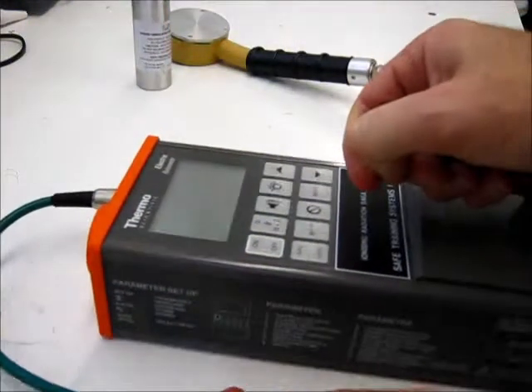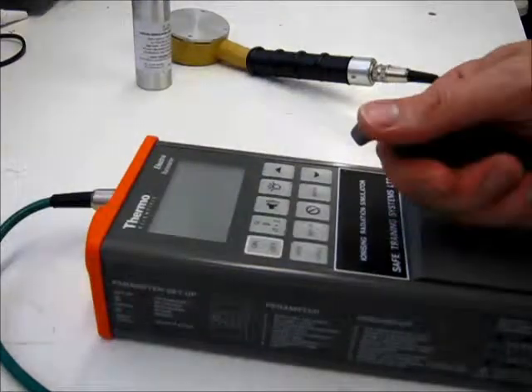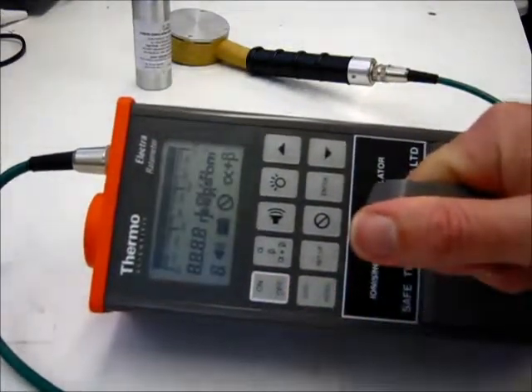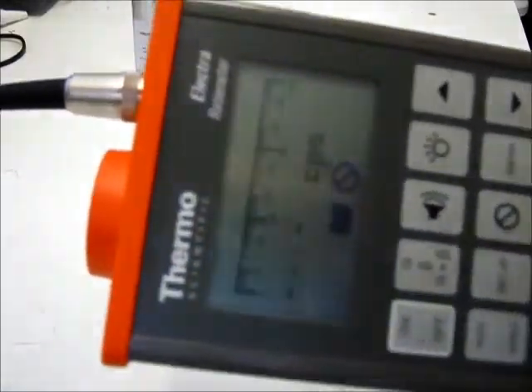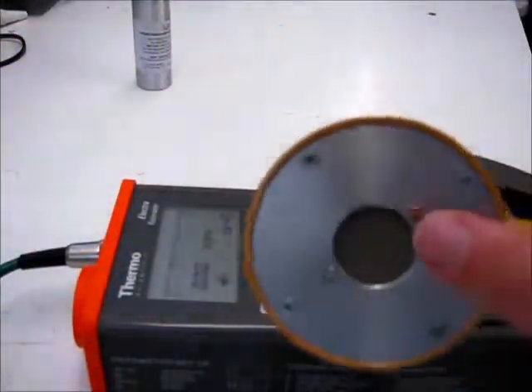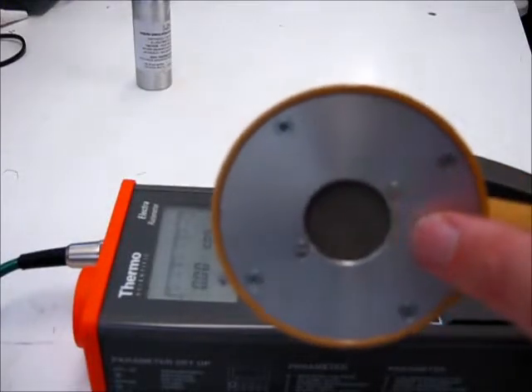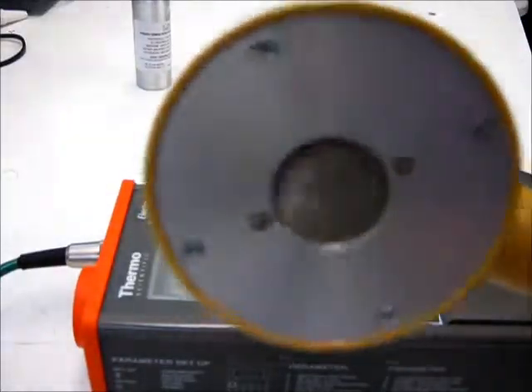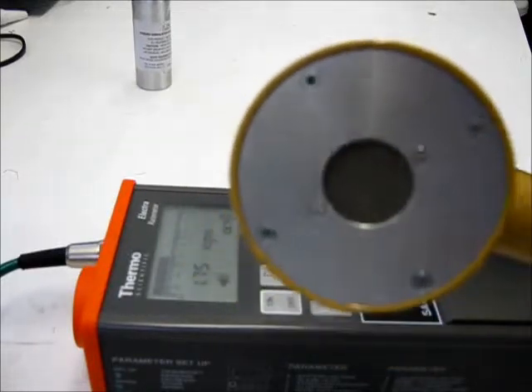Having connected the probe to the instrument, we can then turn the instrument on, and the instrument will go through a series of self-checks and initially display 0 counts per second. Whilst this is happening, the probe is being initialized, and what happens here is that the probe has an electrical current running through it and a fan inside. These take about 30 seconds to a minute to warm up, so you need to leave the probe for at least 30 seconds before you start monitoring.